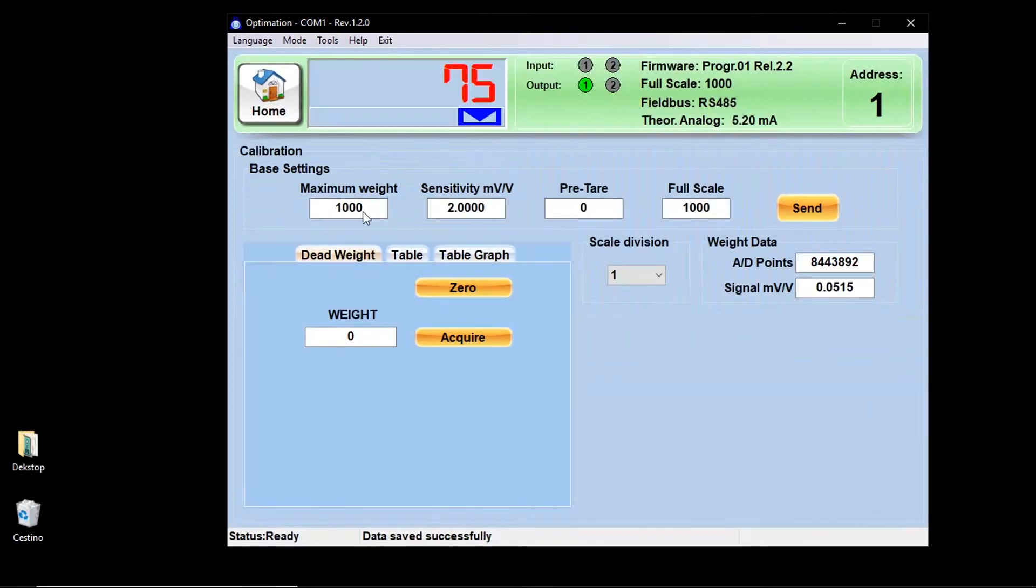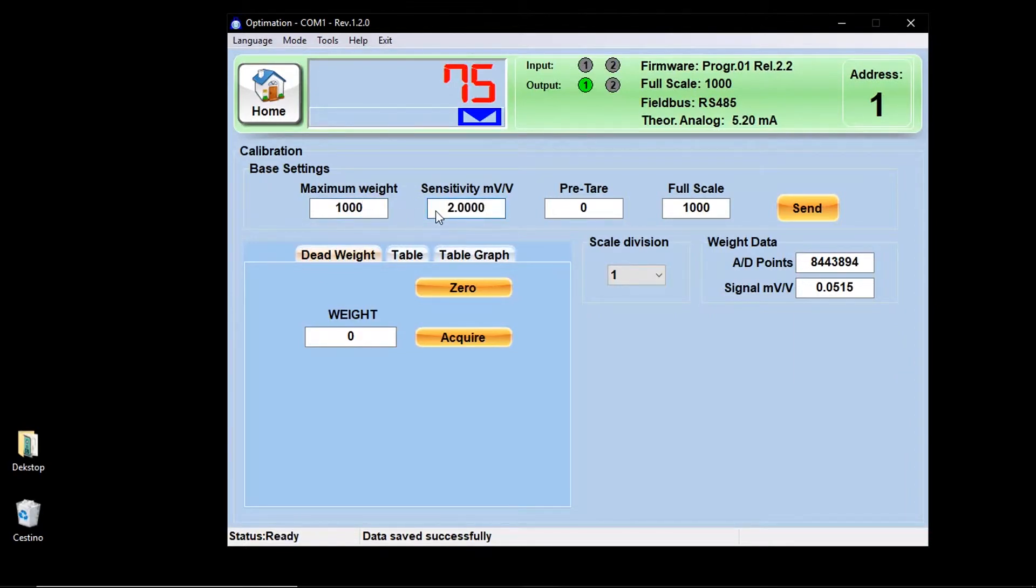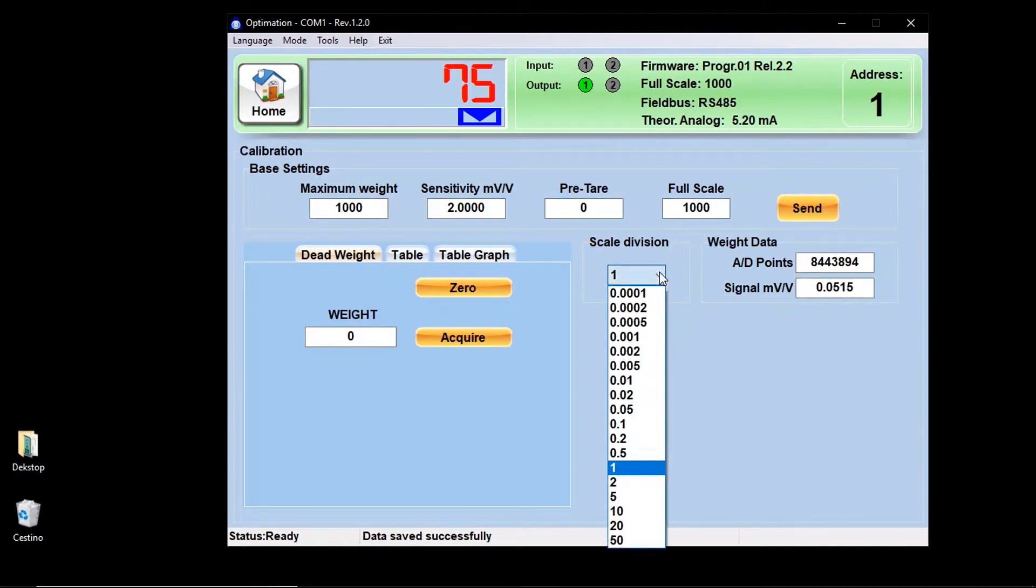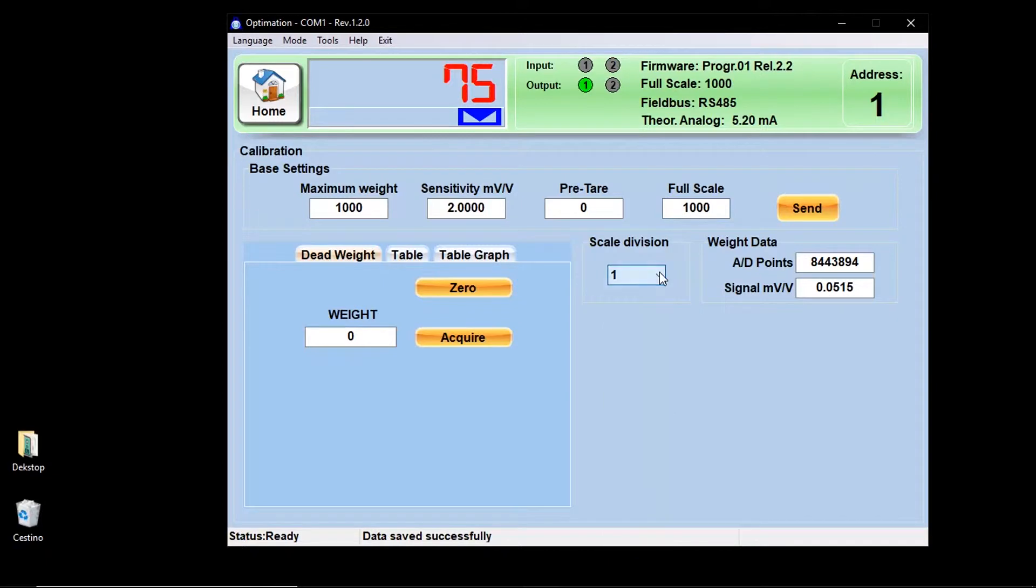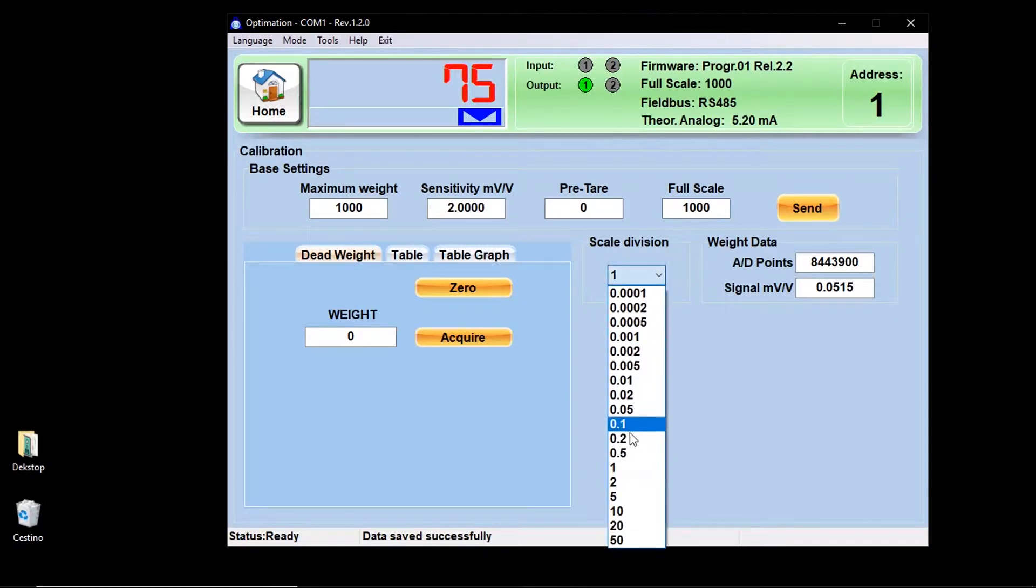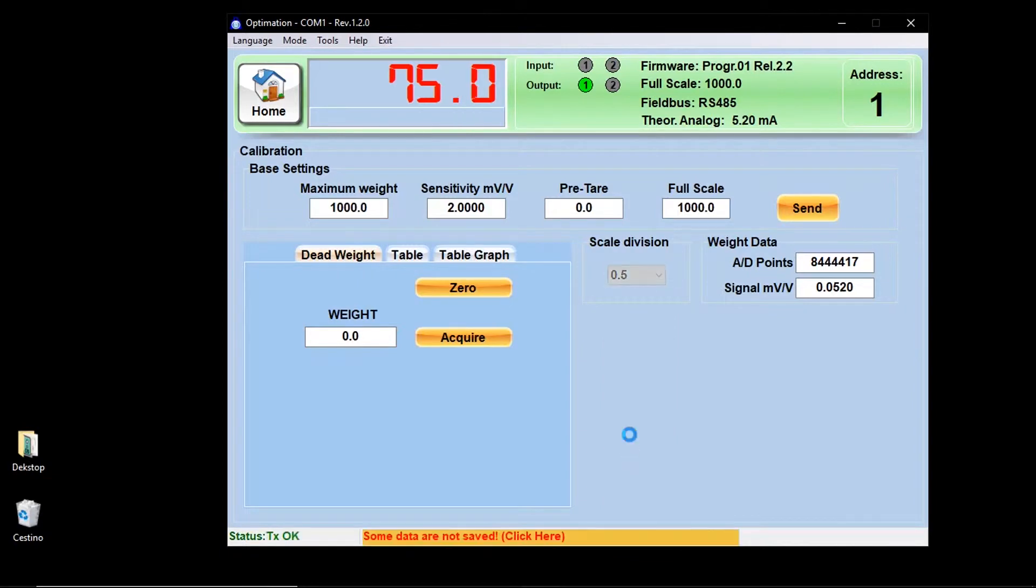The first menu is calibration. Here you have to configure several parameters: the maximum weight of the system, the average sensitivity of the load cells, a possible pre-tare, a full scale of work, and a scale division. Once these main parameters have been entered, the instrument will perform a theoretical calibration.